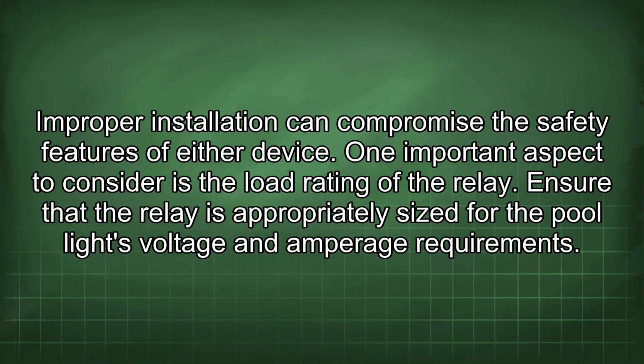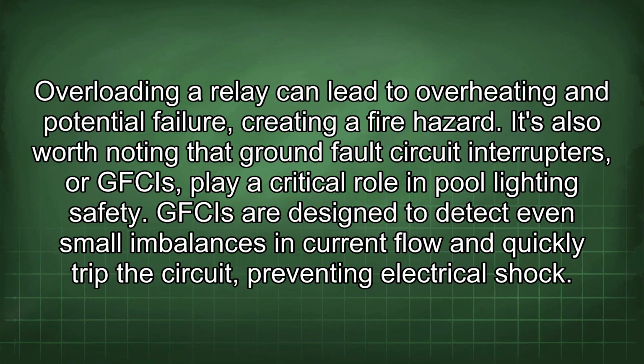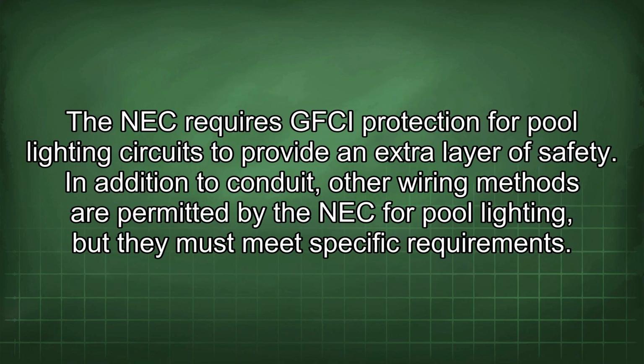One important aspect to consider is the load rating of the relay. Ensure that the relay is appropriately sized for the pool light's voltage and amperage requirements. Overloading a relay can lead to overheating and potential failure, creating a fire hazard. It's also worth noting that ground fault circuit interrupters, or GFCIs, play a critical role in pool lighting safety. GFCIs are designed to detect even small imbalances in current flow and quickly trip the circuit, preventing electrical shock. The NEC requires GFCI protection for pool lighting circuits to provide an extra layer of safety.